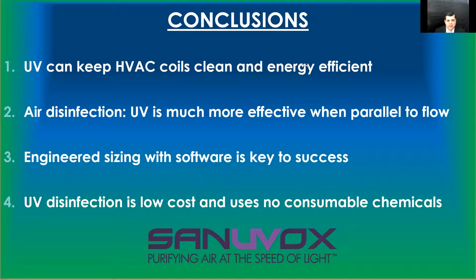Ray Chang asked a question here. Basically, UV is used on cooling coils, but do you need it on heating coils? Yes, you can use them on heating coils, although heating coils are less of a problem for molds. They don't survive the heat very well, and there's no water. So you can do that, but it's just not a big issue for contamination. So most of the time when you have to choose to put UV lights, you put them strictly on cooling coils for that reason.